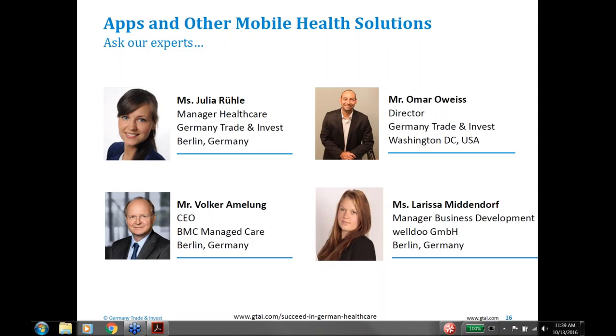Here's a question from a company that has designed a smartphone app which connects to a cloud and monitors patients. In Germany, would they need to get approval from an authority? It depends. That's what I put in the slide where you differentiate the risk classes. At least to my knowledge, a cloud solution is not considered differently than another storage solution. But you have to keep in mind that quite a lot of people, especially on the insurance side, would feel pretty uncomfortable with a cloud solution.